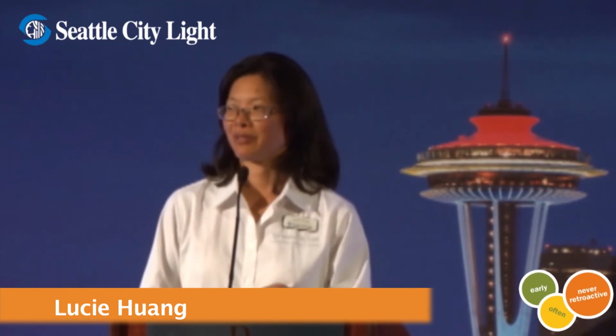Sometimes you propose a certain set point, but the building didn't operate well under that condition. That's fine, we would then adjust the incentive appropriately. If that temperature wasn't achievable, we'd recalculate and provide an incentive based on the new final energy savings.